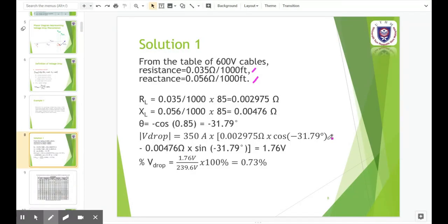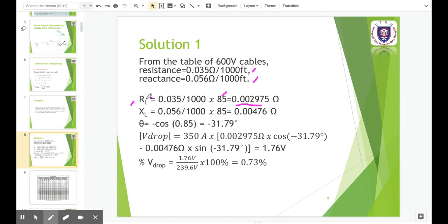Now calculate the actual resistance: 0.035 divided by 1000, then multiplied by 85 feet in length, giving 0.002975 ohms. Then calculate the reactance: 0.056 divided by 1000 times 85 feet, giving 0.004760 ohms.